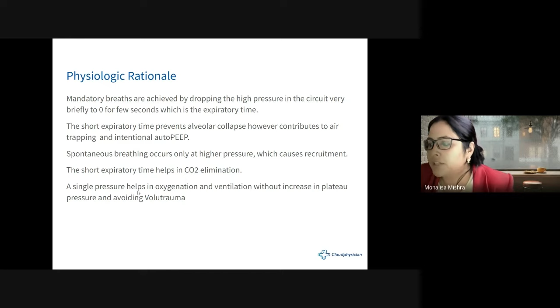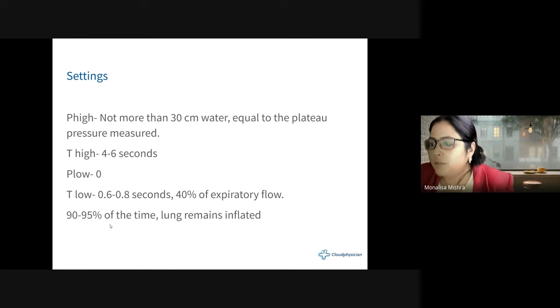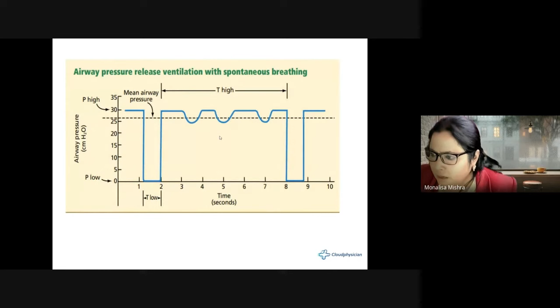Now, what are the settings which we use? P high, not more than 30, which is usually equal to the plateau pressure. T high is 4 to 6 seconds. P low is 0. T low is 0.6 to 0.8 second, at 40% of expiratory flow. 90 to 95% of the time, the lungs remain inflated. So this is just a ventilator graphic of APRV. Now, the last slide about APRV. I'm not going into detail because this class has already been taken.